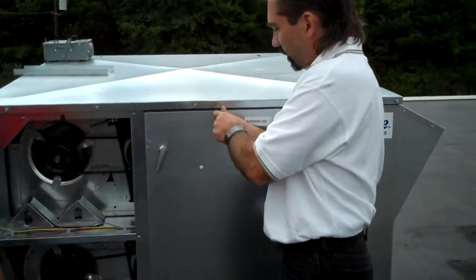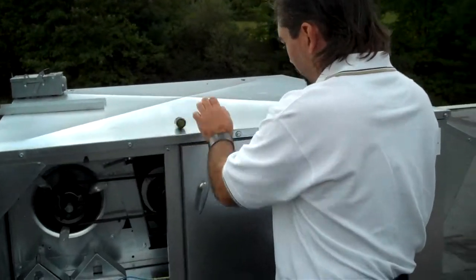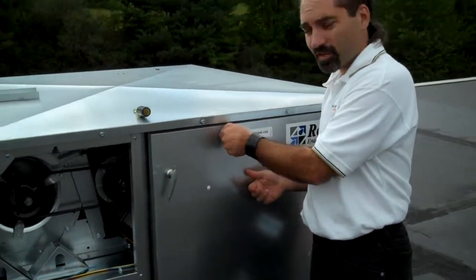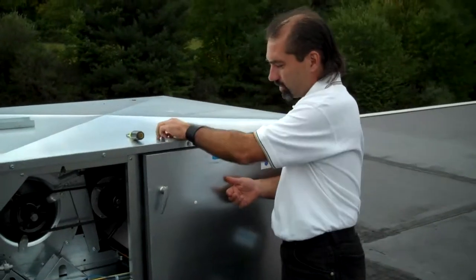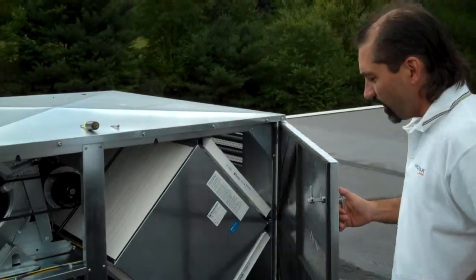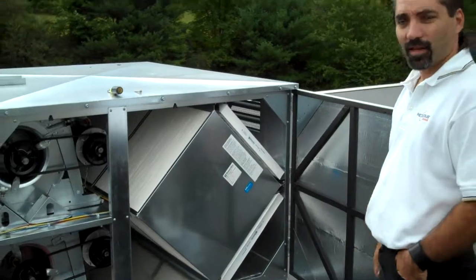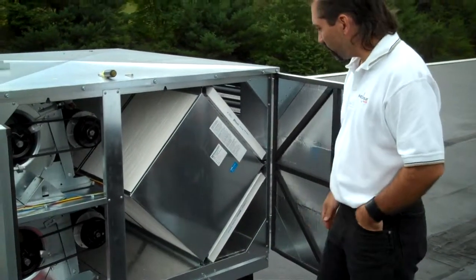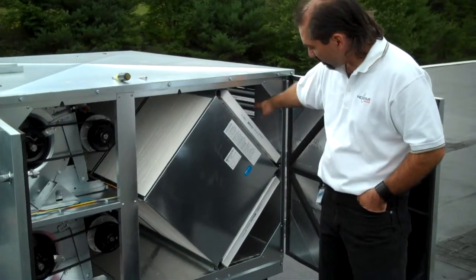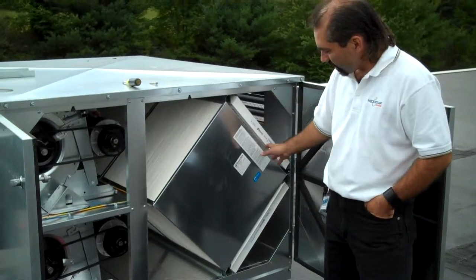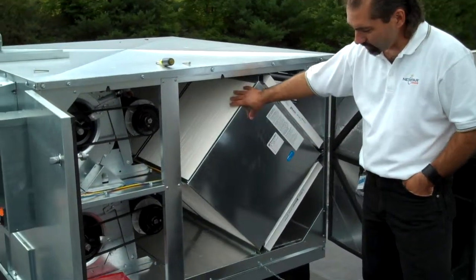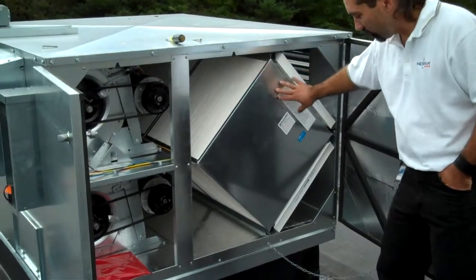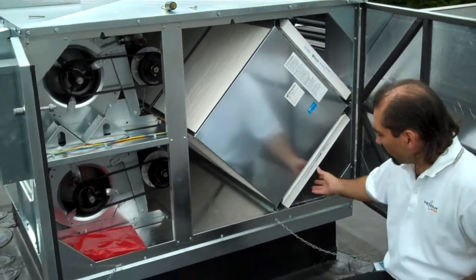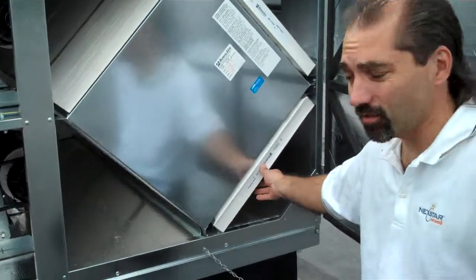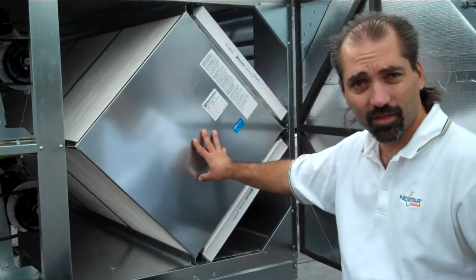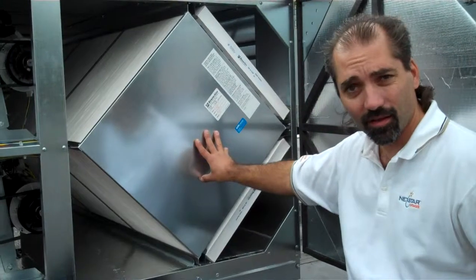Basically what this system will do here, as I mentioned before, is recover up to 85% of the actual energy, heating and cooling energy in the space. So this is connected to the ductwork that we saw? Exactly. This is tied into the duct system that we saw before. And what it does is it brings outside air in through the outside air louver, filters it, and puts it through what's called the core of the energy recovery ventilation system. And it also filters the air that you're exhausting, so it doesn't plug the core up with any dust or debris that's being pulled from the school space.